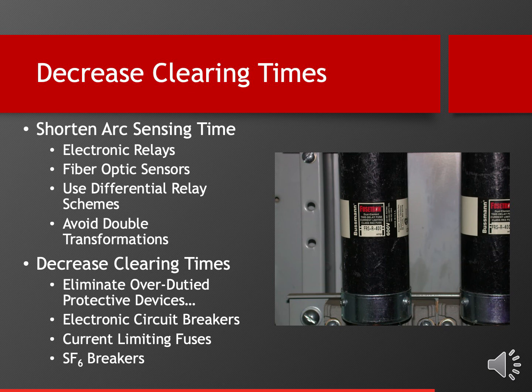And for engineering types, avoid double transformations if you can. So, for example, if you have a system that goes from, say, 12,470 to 480, and you need to go down to 208, it would be better if you could have one transformer for the 12,000 to 480 and a separate transformer from 12,000 to 208, rather than have a transformer from 12,000 to 480 and another one from 480 down to 208. It will turn out better from an incident energy calculation to avoid that if you can. So again, I apologize if that gets too technical for those of you listening. I'm speaking there primarily to the engineers.